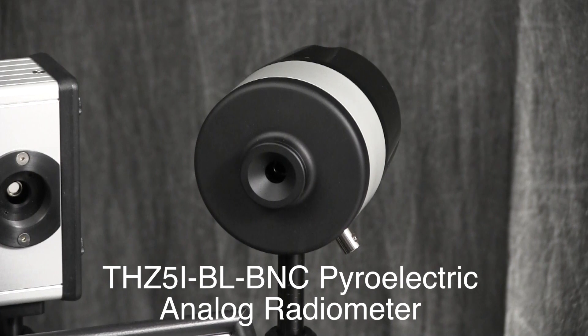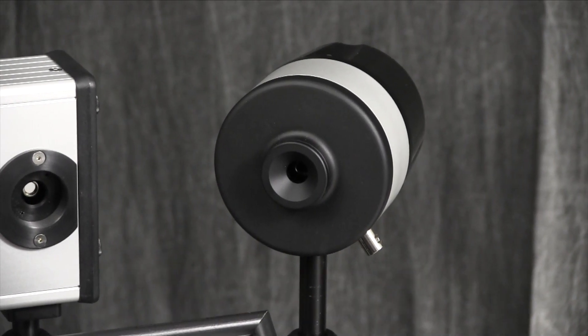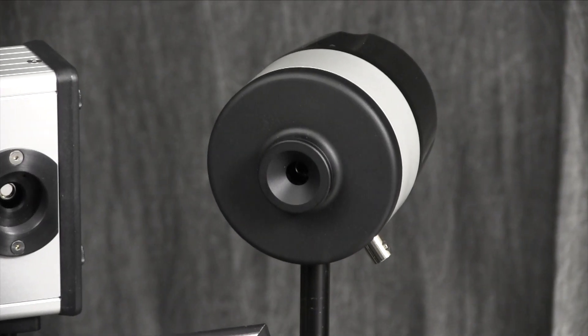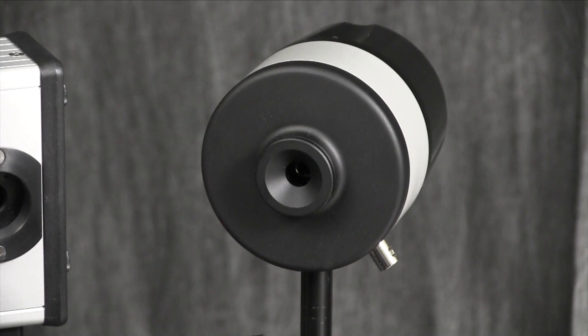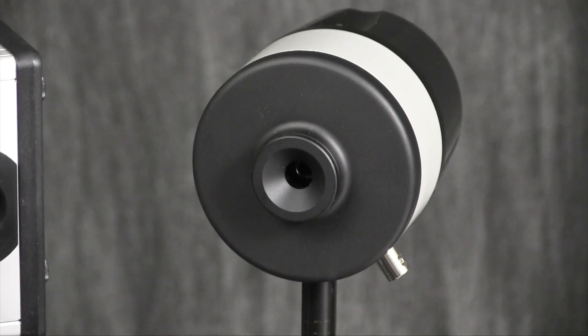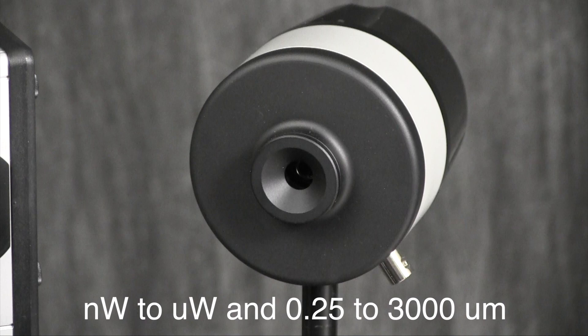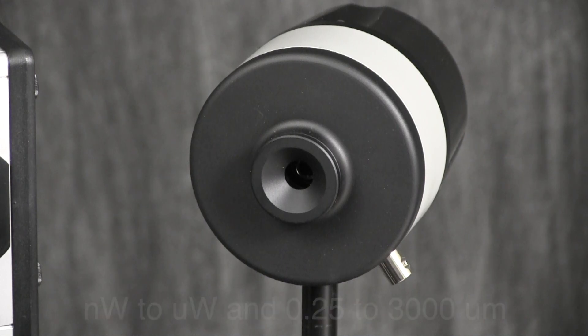We also developed the terahertz 5i BLBNC pyroelectric analog radiometer. It is a self-contained detector, op amp, and power supply in a compact EMI immune metal housing. It features an SM1 threaded front aperture useful for interchangeable windows, light tubes, or IR lenses. Use this with your lock-in amplifier to measure from nanowatts to microwatts and from 0.25 microns to 3,000 microns.